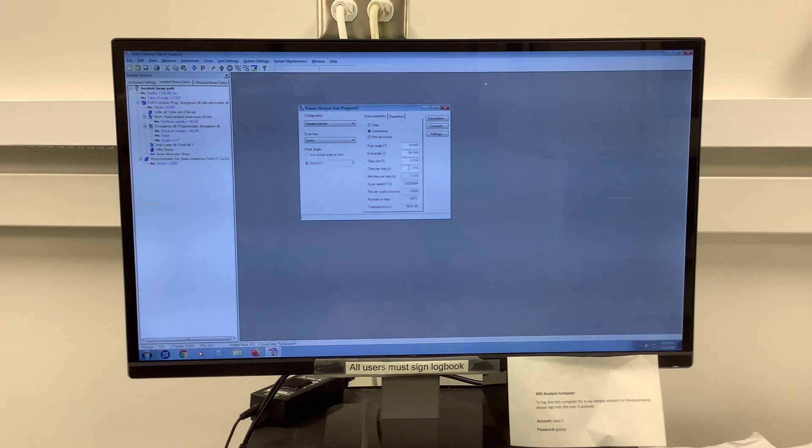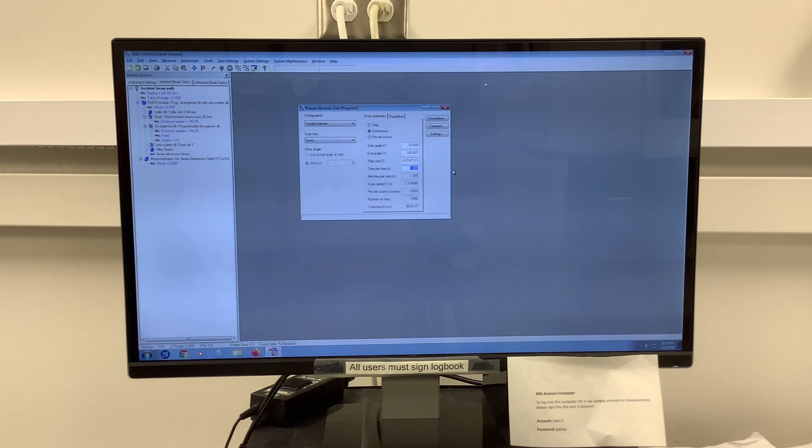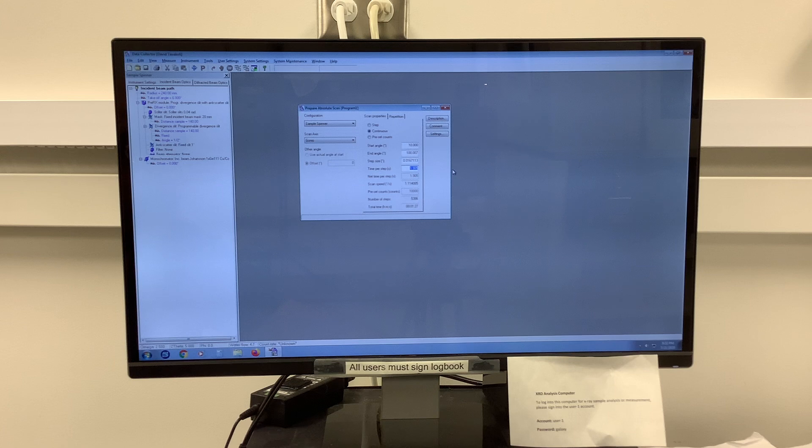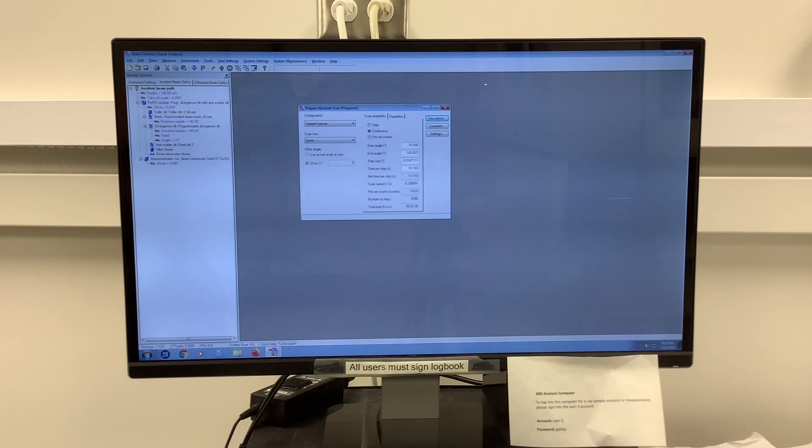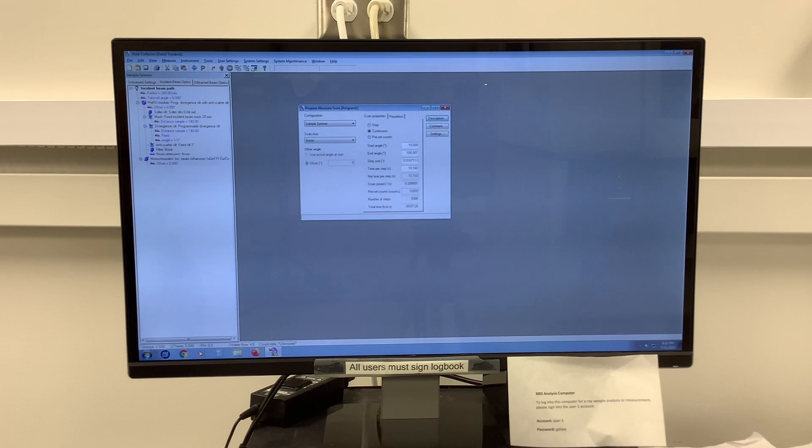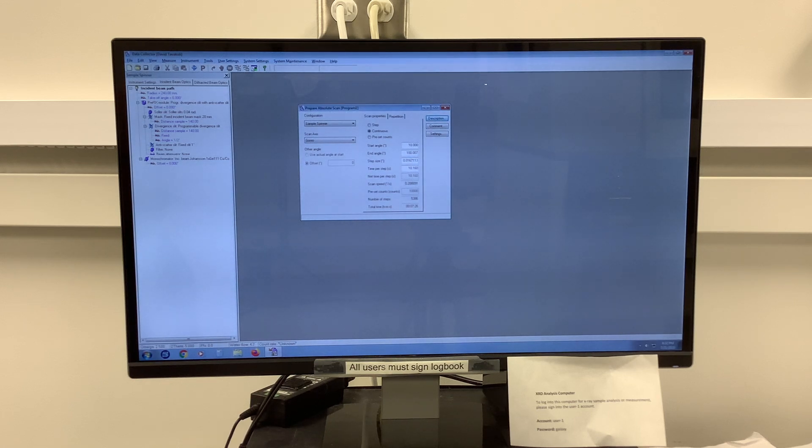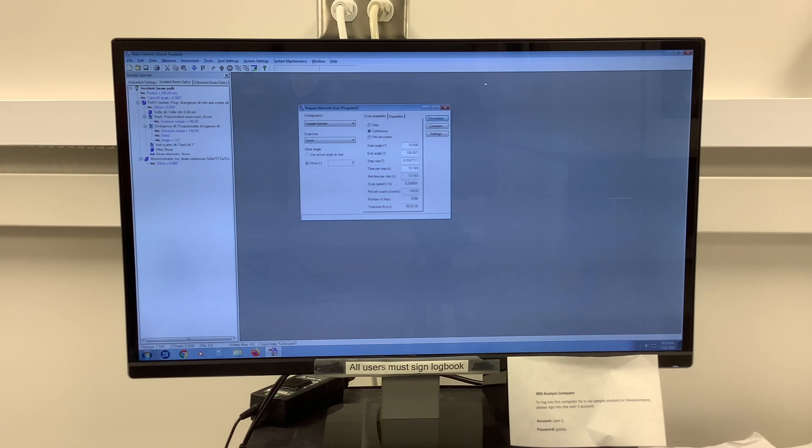If it is an unknown material that I have never measured before, I will do a relatively quick scan to see what I'm looking at, to see whether my intensity is good enough, to see whether my step size is good enough. To do that, I'll make my time per step 10 seconds, and that will give me an average total time of roughly seven and a half minutes. If my first scan is somewhere between four to eight minutes, usually that's a good first pass to see what is good enough. Unfortunately for X-ray diffraction, there's no magical program that will give you everything you need. You'll always create a first program and iterate based upon your material and your counts to get to where you need to go.